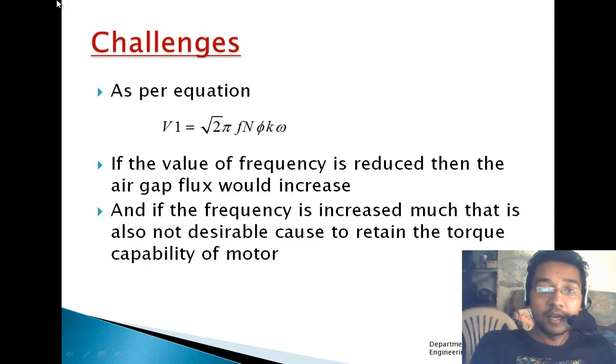Now, if I reduce the frequency, probably my flux would be increasing, which is not desirable because increasing the air gap flux would saturate the magnetic circuit of the induction motor. If I increase the frequency, that would reduce the flux, which is also not useful for retaining torque capability. So I'd rather go for V by f control, with simultaneous control over voltage and frequency so both are maintained at level.